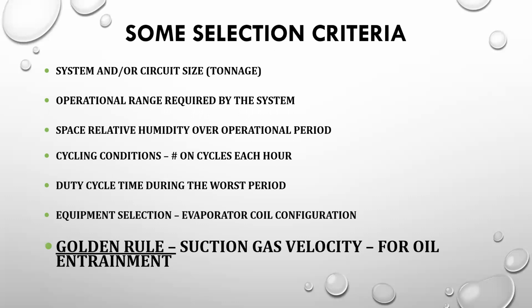Selection criteria: system or circuit tonnage, operating range, space relative humidity over a period. In other words, if it's 85%, you've got a huge issue. Cycling conditions: how many times does it cycle an hour, and how long does it stay on? The duty cycle during the worst period, I've seen them cycle on for 3 minutes and kick off. Evaporator selection: this can be critical, because if you've got a package unit or split system with a split face evaporator, there are other things you have to do, and you may have to add 2 valves. Golden rule: suction gas velocity.